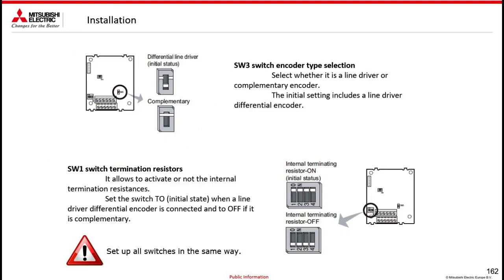As far as the installation is concerned, it is very simple. There are simply two switches to pay attention to. One defines whether the type of encoder is line driver rather than complementary, so open collector, and the other activates or not an internal resistance, which depends on the encoder type. If it is of the line driver type, then on.